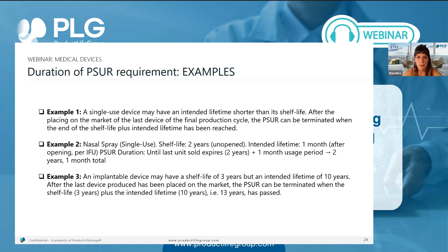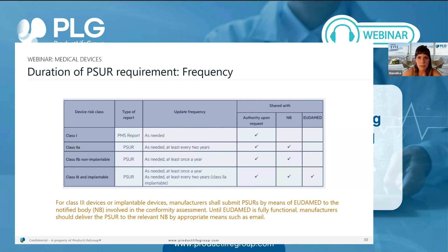And here is a summary of what the requirements are and where the manufacturer should notify the PSUR according to the class. So class 1 should be available upon request. Class 2, and class 2A and 2B for non-implanted devices, should be communicated and sent to the notified body, and until EUDAMED is fully operational and functional, they should be sent by email if it's possible. And class 3 and implantable devices should be done through EUDAMED when this is functionally available.